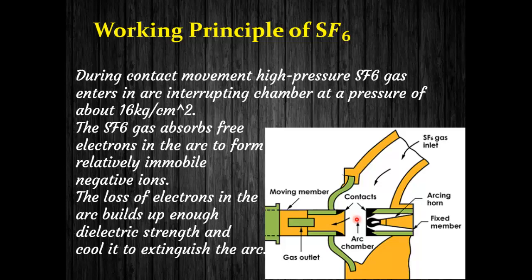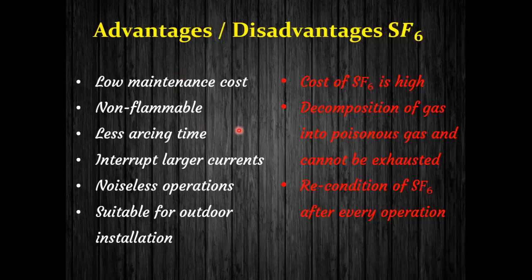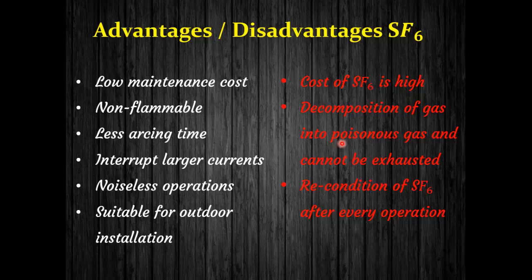The advantages of the SF6 circuit breaker include low maintenance cost, non-flammable gas, very short arcing time, ability to interrupt large currents due to high dielectric strength, noiseless operation, and suitability for outdoor installation. The disadvantages are that the cost of SF6 gas is very high, and decomposition of the gas results in poisonous byproducts which cannot be exhausted into open air, requiring reconditioning of the SF6 gas after every operation.